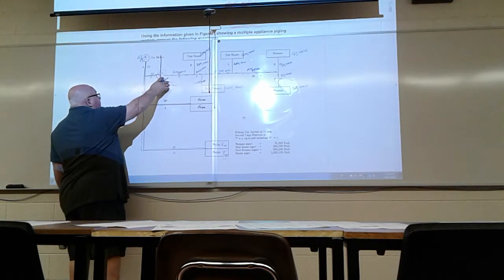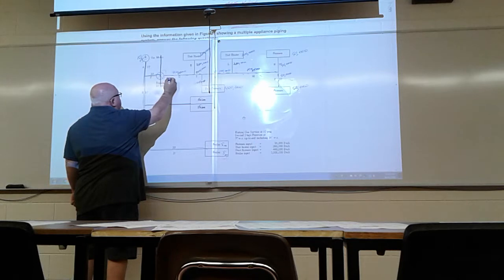Everybody good so far? Okay. So our regulator does not decrease the flow, it decreases the pressure. So if 900,000 BTUs has to come out of the regulator, 900,000 BTUs has to go into the regulator. That's on the high pressure side.